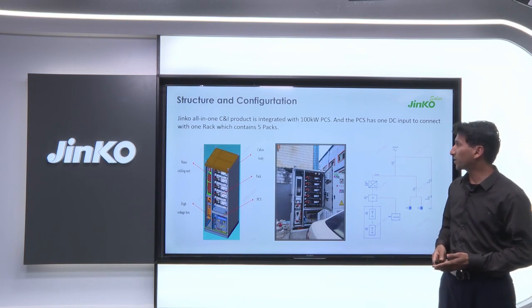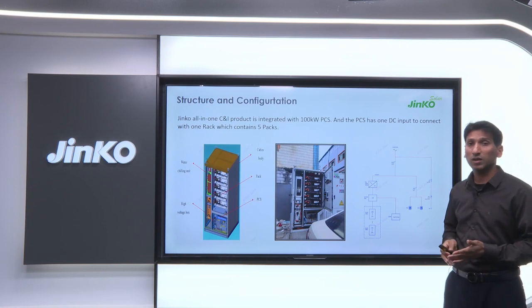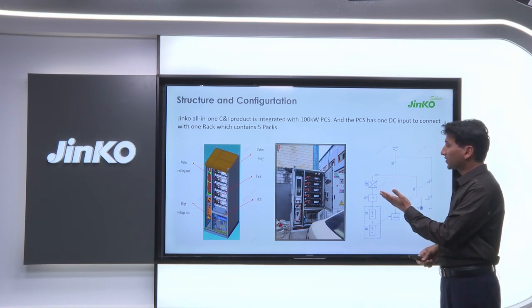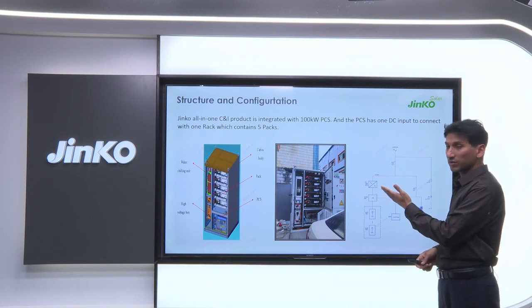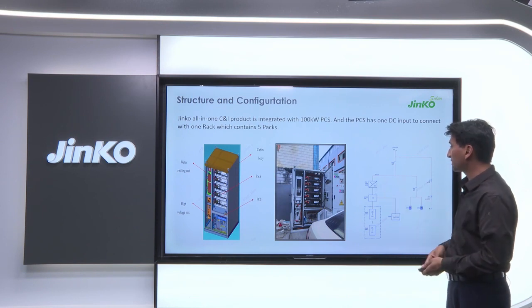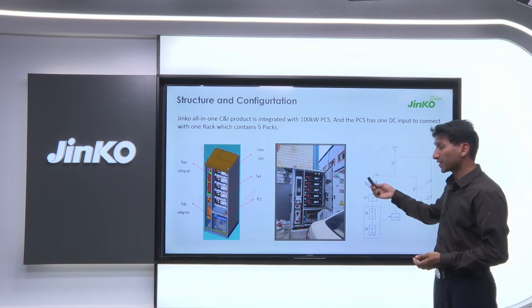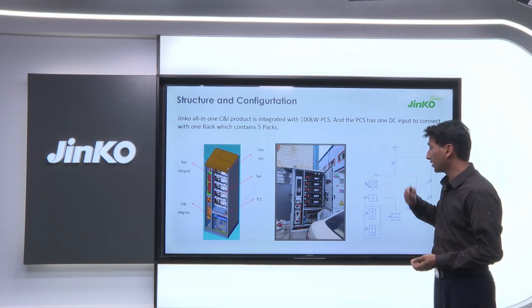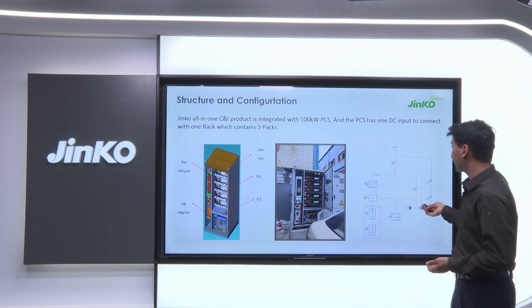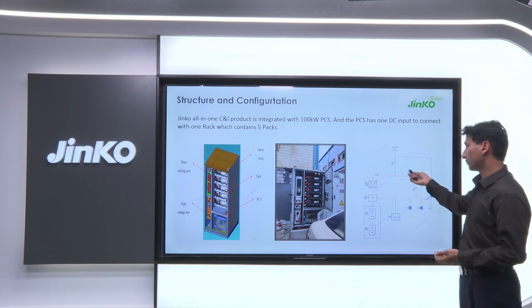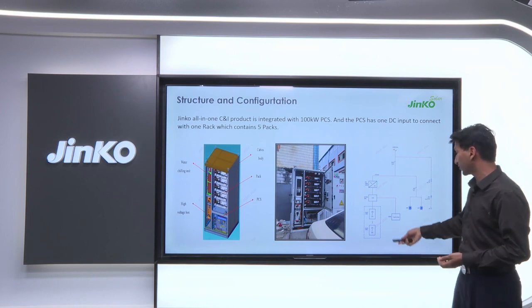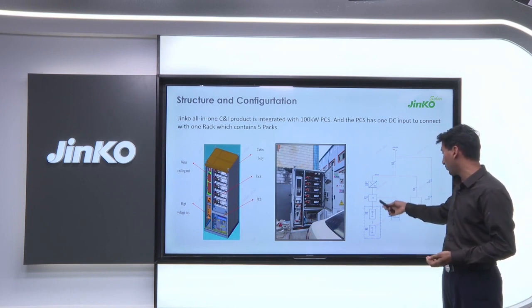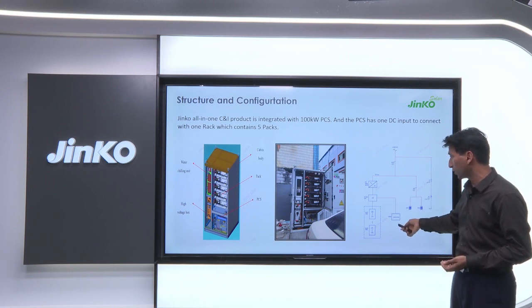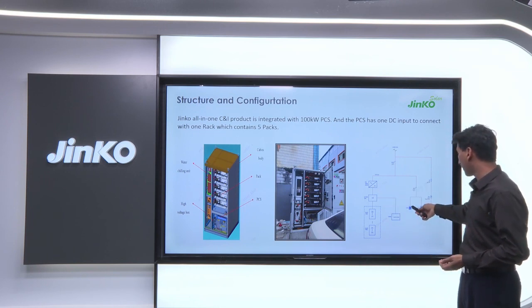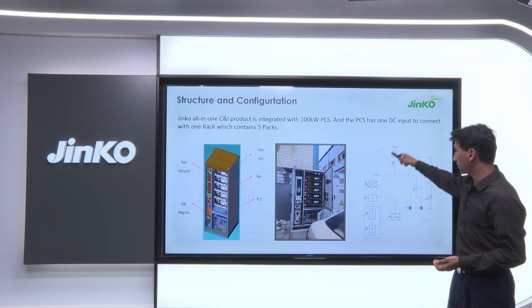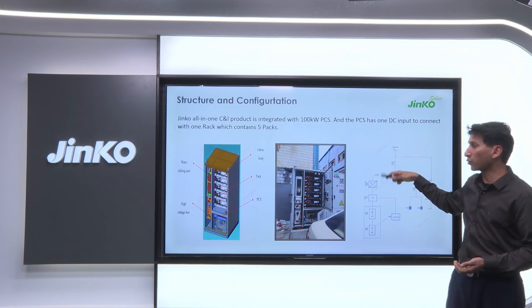Starting with the first place, we look at the structure and configuration of our cabinet. On the left side is a 3D model of our SunGiga cabinet. In the middle is a picture I have taken of one side of the master cabinet. Why I call it a master cabinet, I will tell you later. And this is the SLD, single line diagram, for our master cabinet, where you can see the batteries connected to the high voltage box, which supplies power to the liquid cooling system, then connects to the AC, which supplies power to the fans, and then we connect to the main supply for the input and output power.